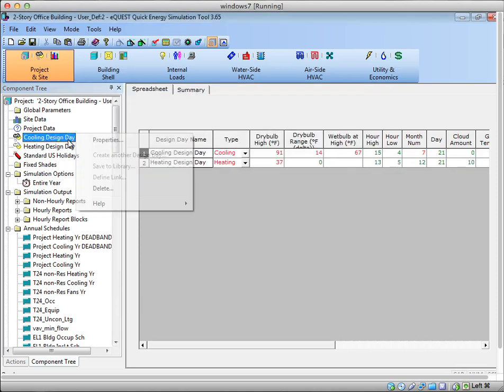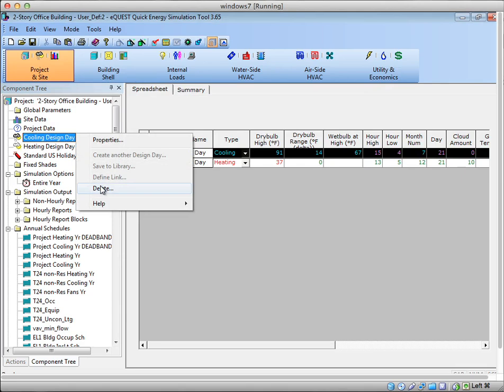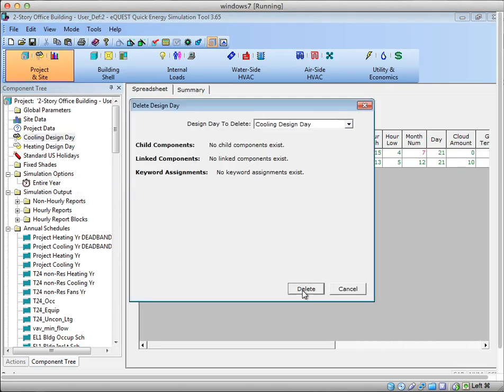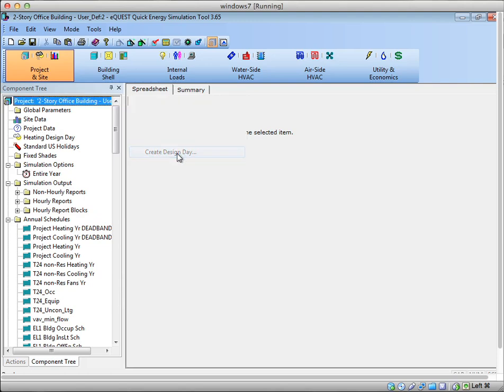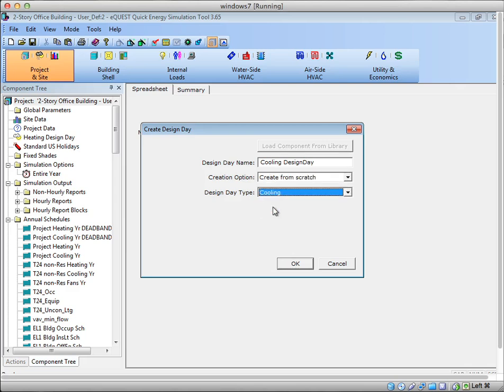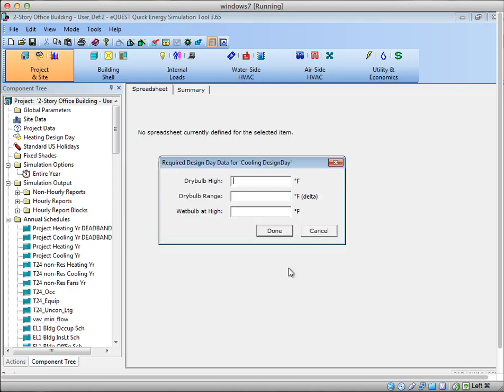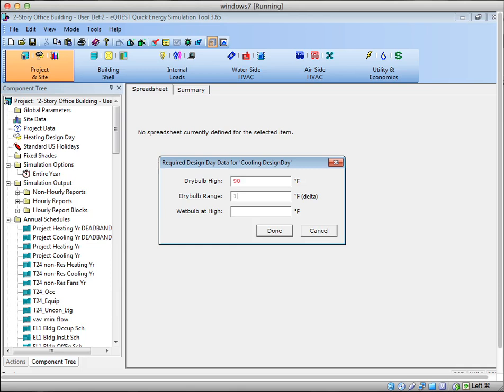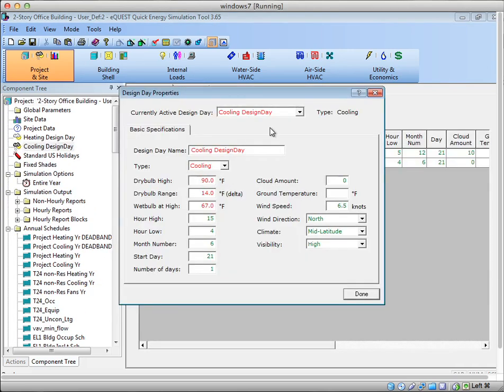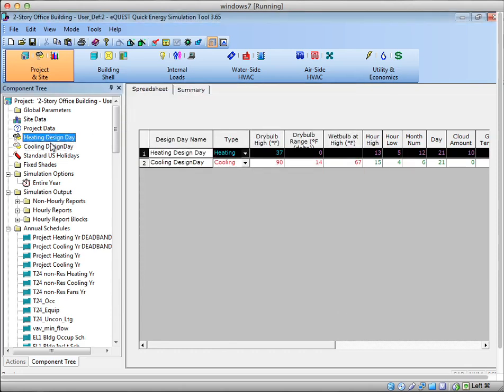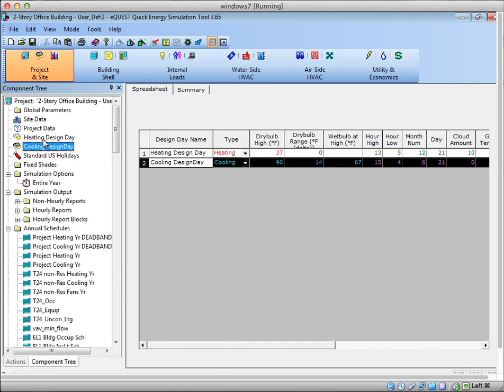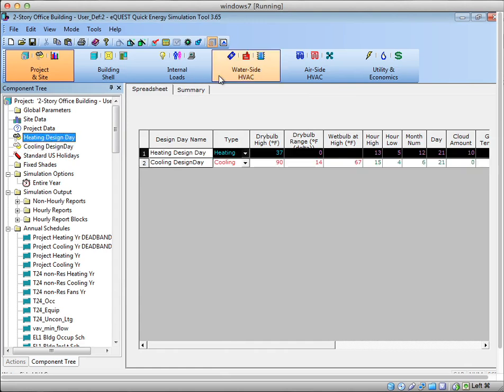If you don't have any of these, let me actually delete one. If there is no design day there, now we just have heating design, you can actually right click on the project tree and say create design day. This will only show up if you don't have one of the two there. So I can say cooling design day. I will pick the cooling type, hit OK. And now it's got a problem for some input. So if you do this before you actually know these numbers, just pick some fillers because eQuest loves to freeze you up unless you actually put in values. So there I put in some default values and we're done. So now we have two design days.